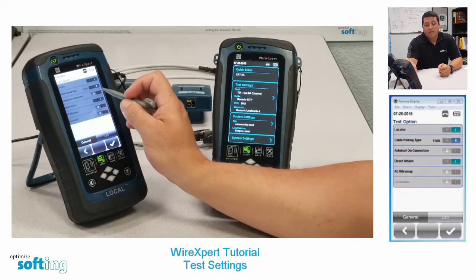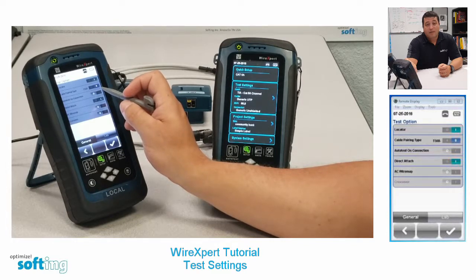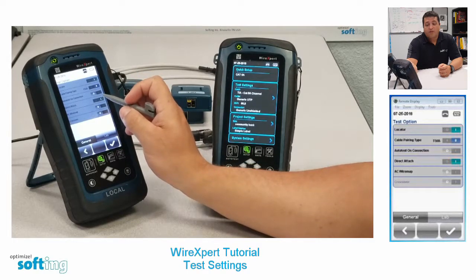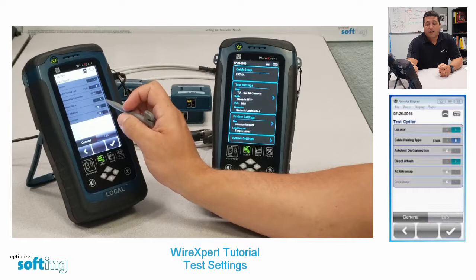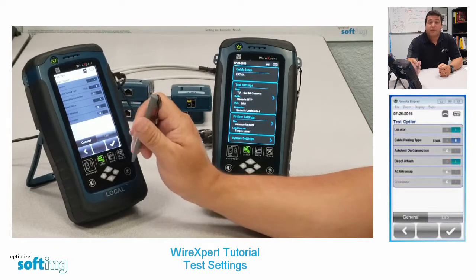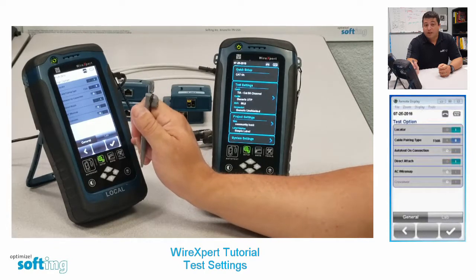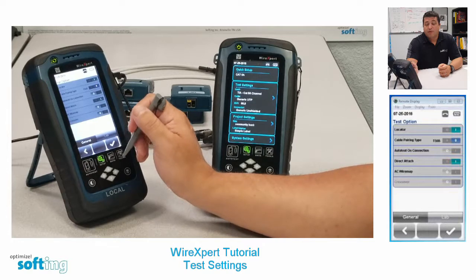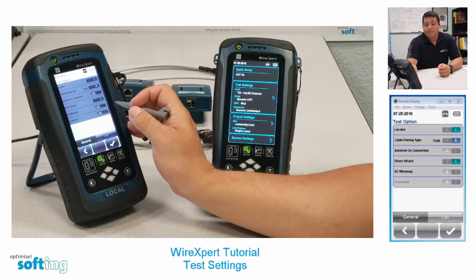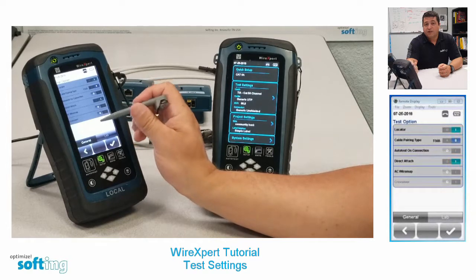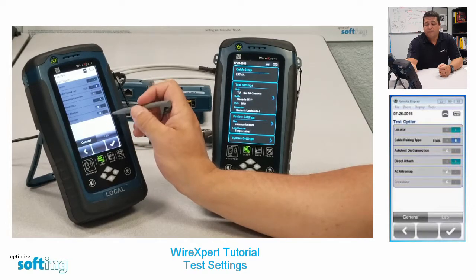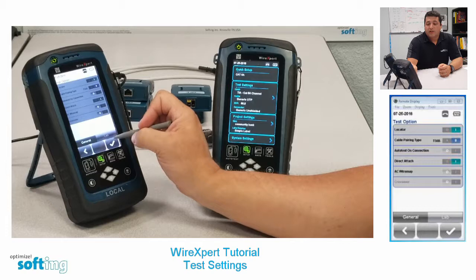In North America, most of our pairing is going to be 568B. For auto test on connection, we suggest that you have that off for most testing applications. Direct attach you want on — that gives you the ability to do MPTL testing, which has been newly ratified through TIA. AC wire map you want to have off more than likely, unless you're testing POE through mid-span.